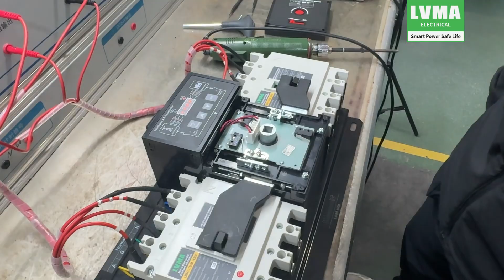After successful opening and closing, test the trip function to ensure it operates correctly. When tripping on the backup side, set the main side to close. When tripping on the main side, set the backup side to close. If both sides close normally, the preliminary testing is complete.